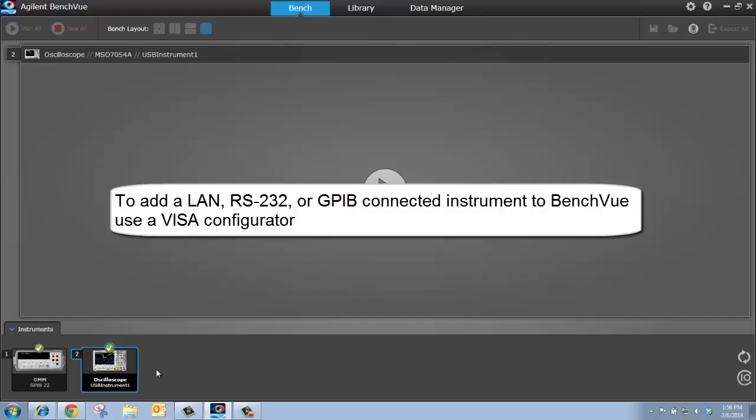Now for LAN and RS-232, to add them to BenchVue, we need to use a VISA configurator, which I'll demonstrate. And once we do that, in the future when we open up BenchVue again, they will automatically show up on our instrument panel as long as they're connected to the computer. So let me demonstrate that. If I go over to this IO icon, I can open up a VISA configurator on my computer.